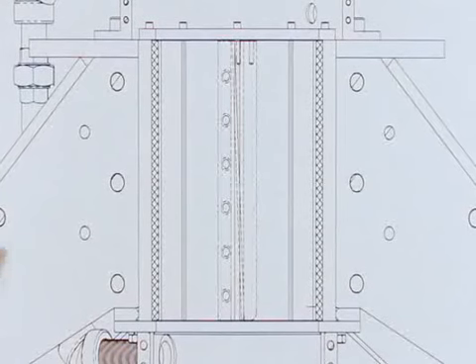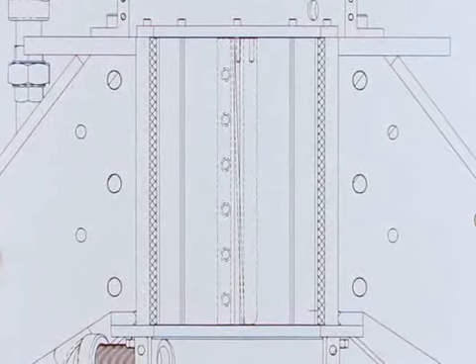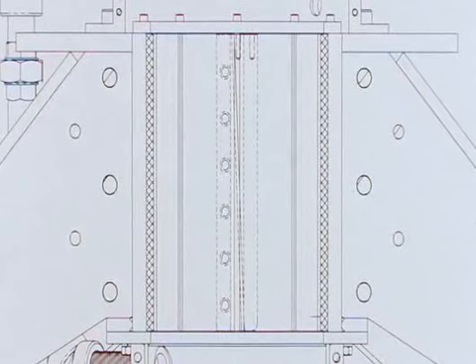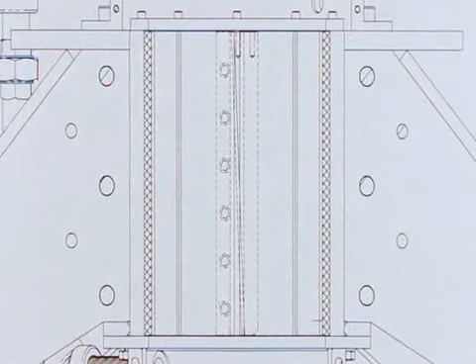The water-lubricated bearing is made in 2 replaceable halves. A split and tapered bronze key set is used to lock the bearing in place and permits quick and easy inspection or replacement with no major disassembly.